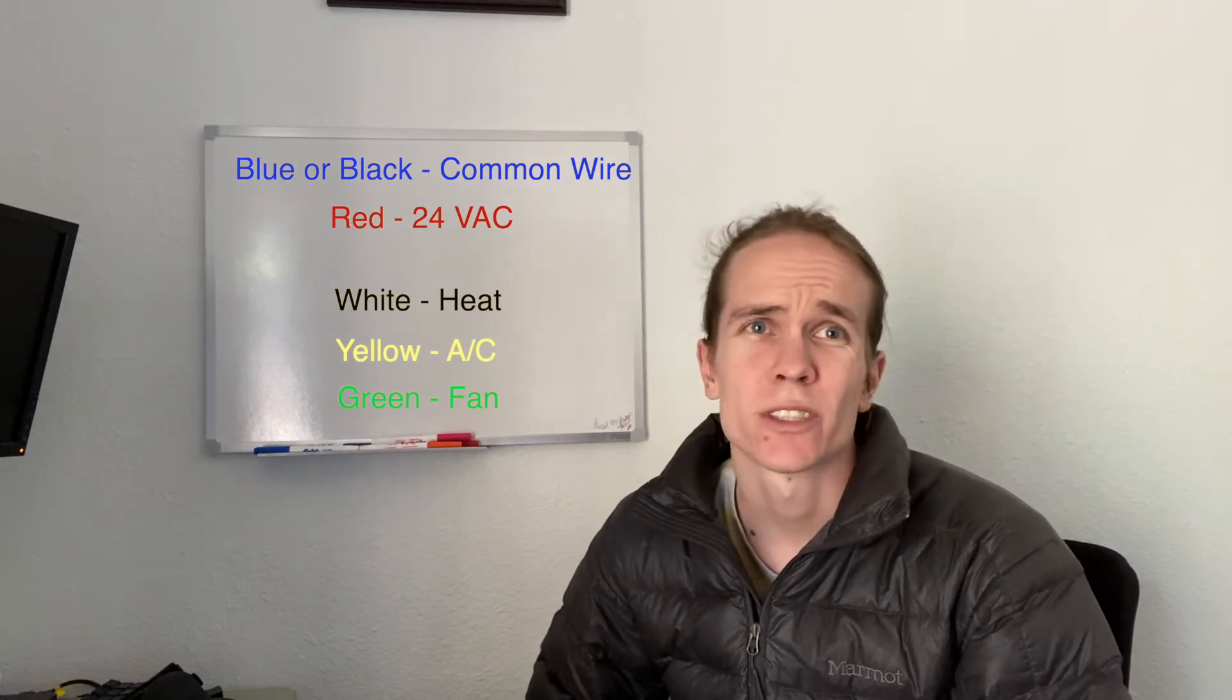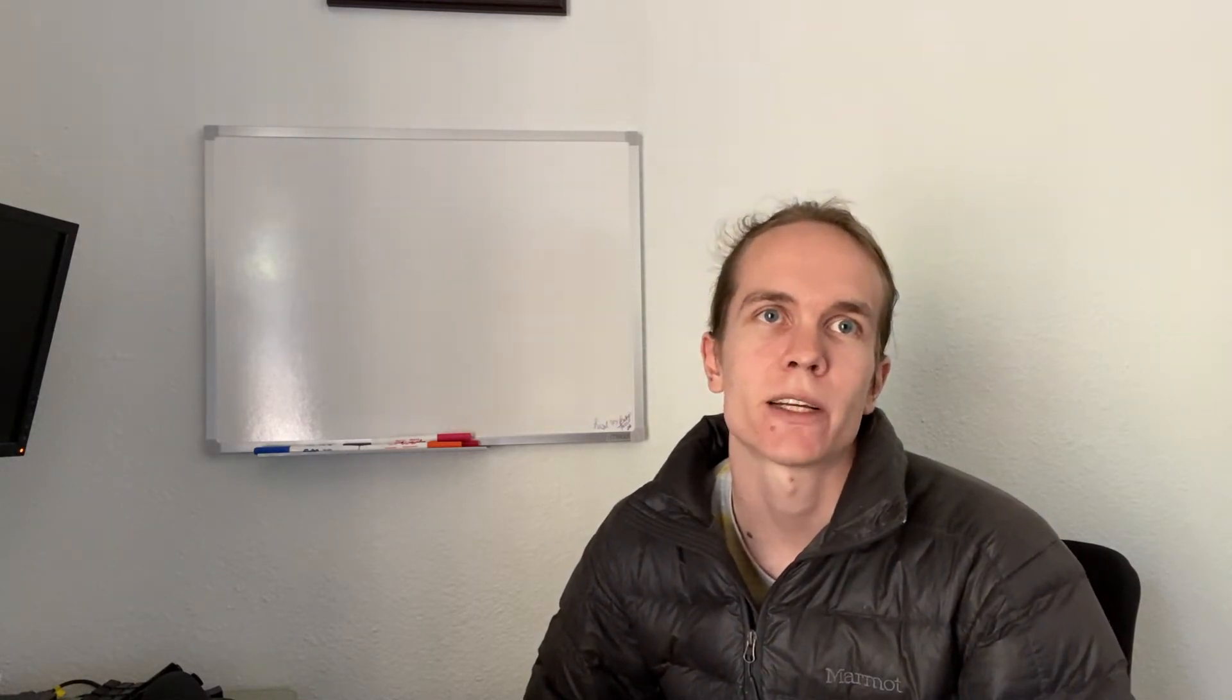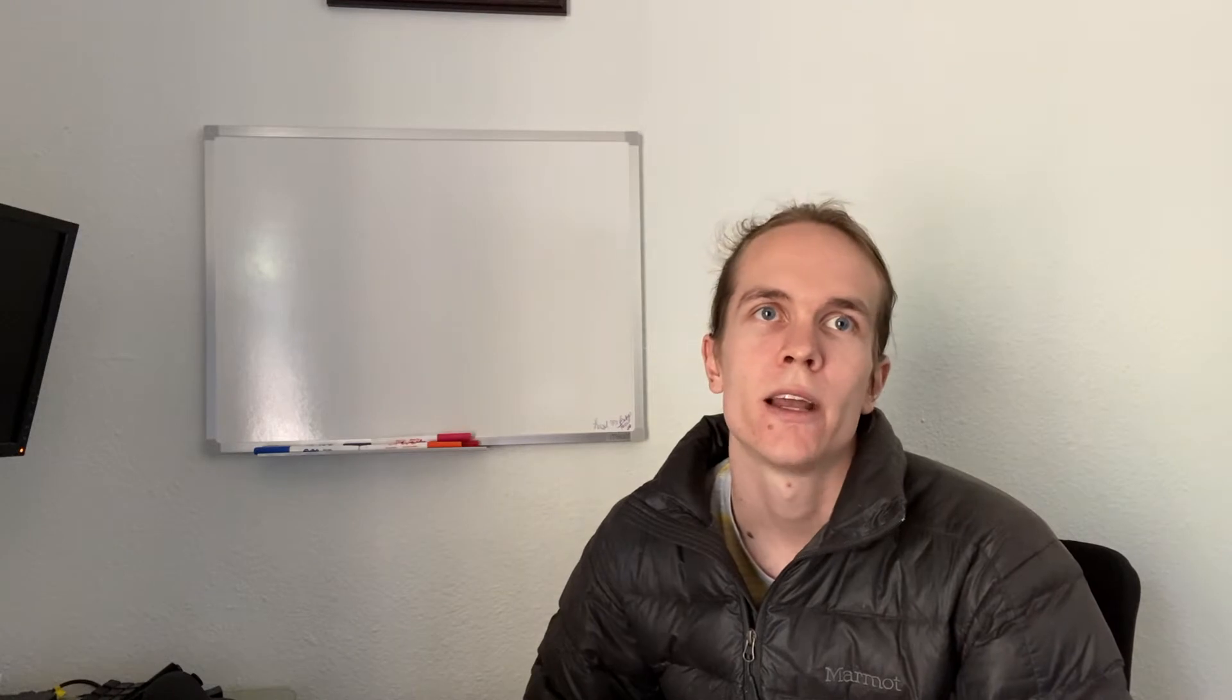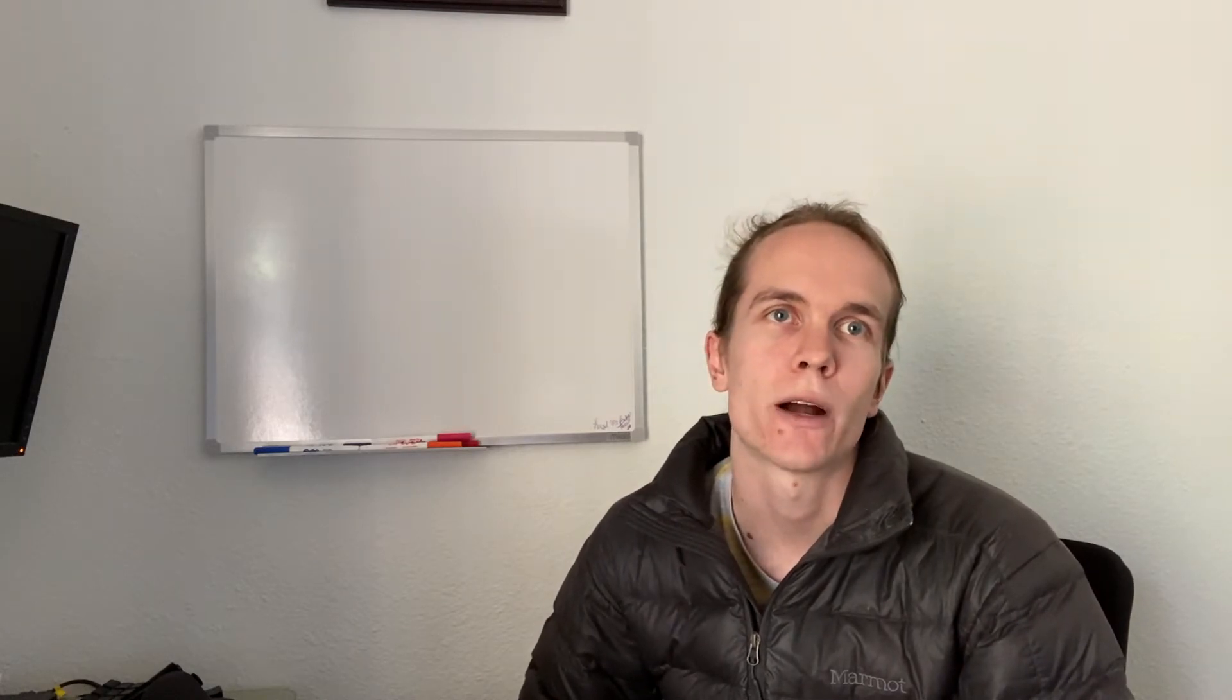In some older systems and some higher end systems, you're going to have a RH wire and an RC wire. Those are just dedicated powers for your heating and cooling system. But most systems don't have that. If your system does have that, most smart thermostats have a place to plug it in. So it's not a huge issue one way or the other.